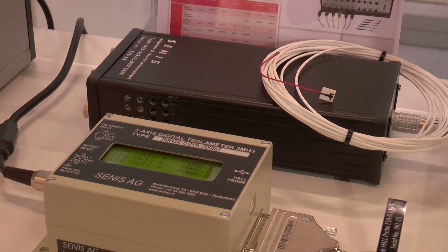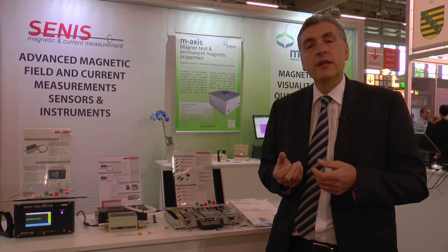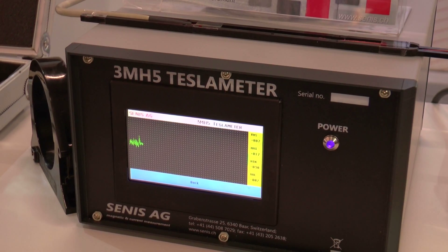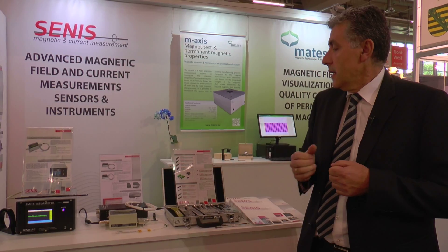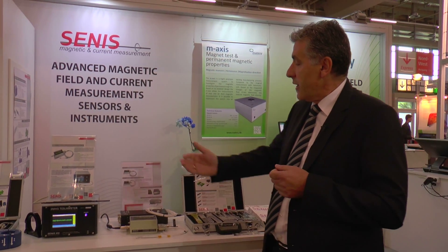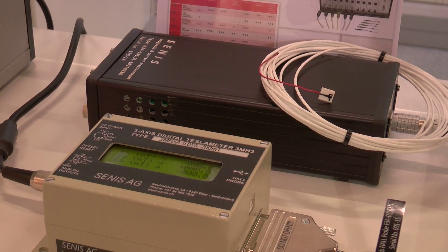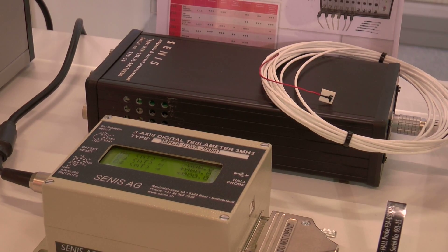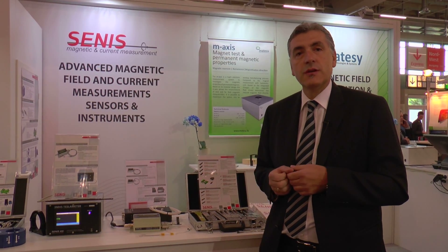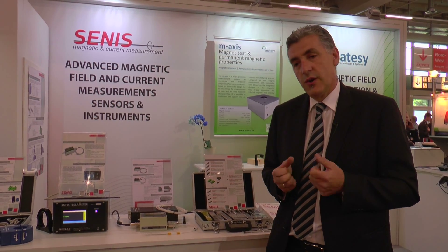Besides hall probes, SENIS utilizes AMRs — magnetoresistive sensors — for example for our nanoteslameter. The magnetic field measurement probes are connected to an electronic module providing power supply and measured signal conditioning, such as residual offset cancellation, further temperature compensation, linearization and so on.